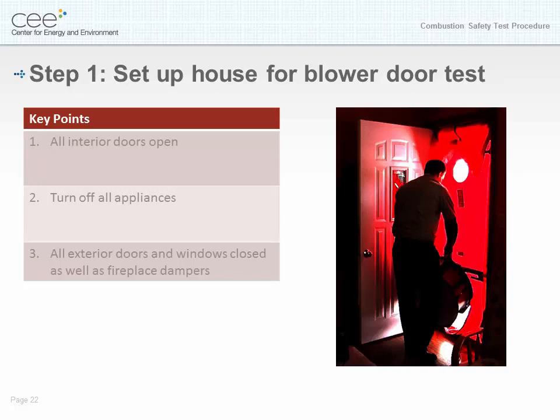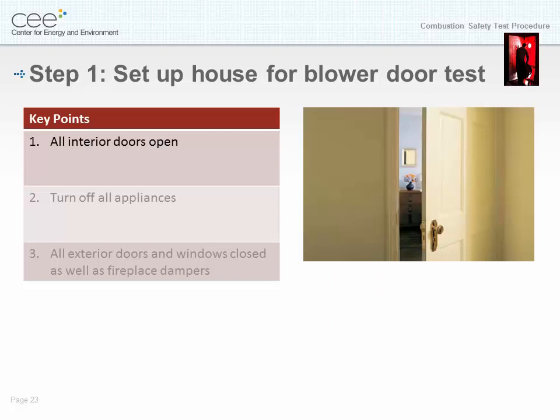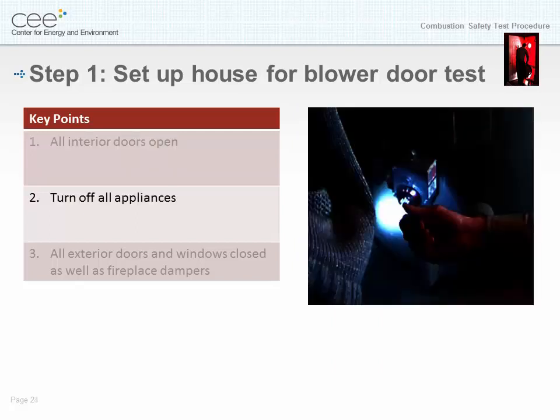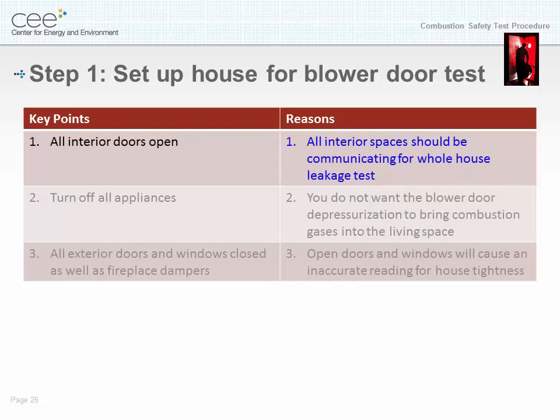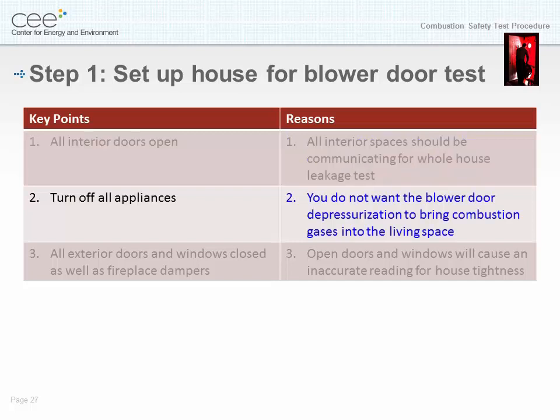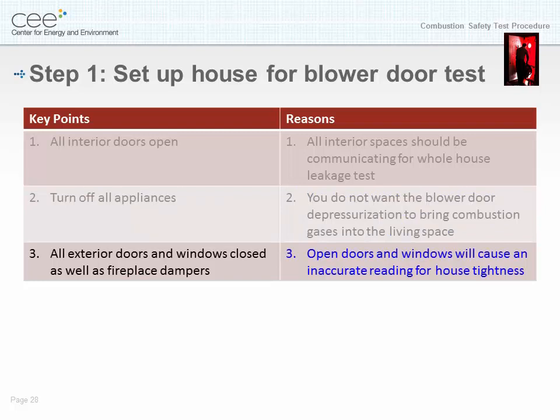Step one: set up house for blower door test. Key points: all interior doors are open; turn off all appliances; all exterior doors and windows are closed as well as fireplace dampers; all interior spaces should be communicating for whole house leakage test. You do not want the blower door depressurization to bring combustion gases into the living space. Open doors and windows will cause an inaccurate reading for house tightness.